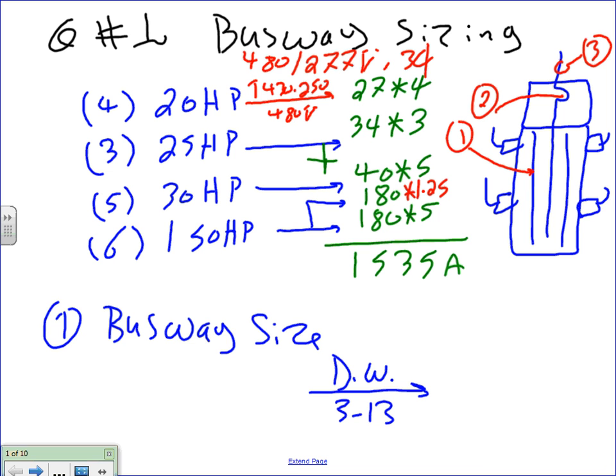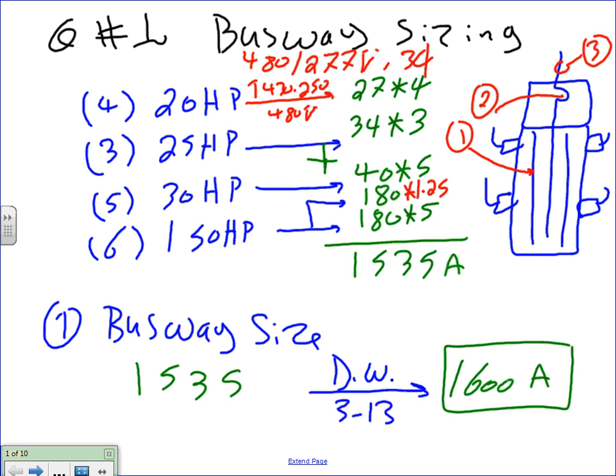Tom, my friend, if you take the 1535 amps and you take them to the semi-industry standard from DeWalt, they'll give you all the listing of the plug-in and feeder busways. If you guys go there, 3-13, which you should have, you should end up with 1600. The next standard is 1600 amp, 1600 amp plug-in busway. So you guys are gonna grab this number tomorrow from DeWalt, because that's not in the code. You're not gonna find it in the code. 1600 amp. Any question, guys?